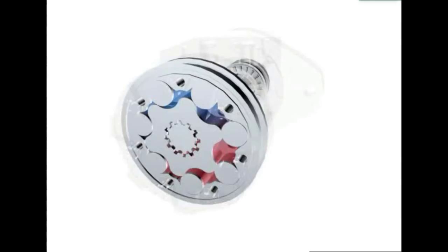The rotary valve ports fluid from the inlet to the high pressure cavity between the gears. Fluid from the low pressure cavity is ported back through the rotary valve to the outlet. Fluid enters the high pressure cavity and pressure builds. The rotor tooth is forced off the roller tooth. This causes the rotor and the rotary valve to rotate slightly. The output shaft, which is connected to the rotor by the drive coupler, also rotates slightly.